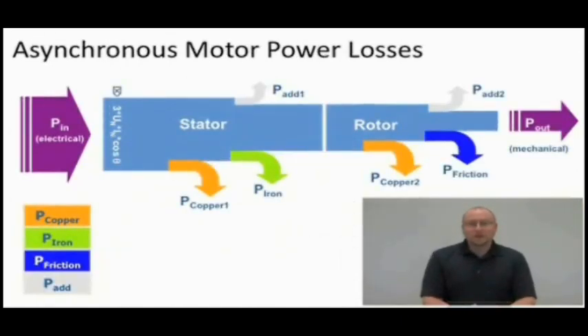Alright, the next components that we're going to talk about are the motor and the gearbox. We're going to talk about the motor first, but the majority of all losses are heat, especially in the motor and the gearbox. In an asynchronous motor, we're going to have some of the same losses that we've had for any electrical component. We're going to have copper losses. But there's a couple of other different losses in an asynchronous motor. You have the friction of the bearings, you have iron losses, you have eddy current losses, you have a bunch of different losses. But really the main loss that we can attack are the copper losses. And then we'll talk a little bit about how to do that in an asynchronous motor.